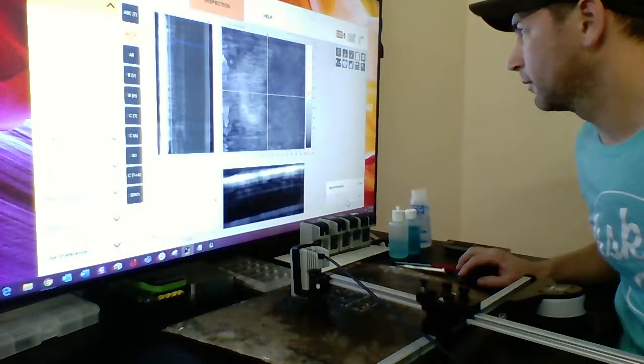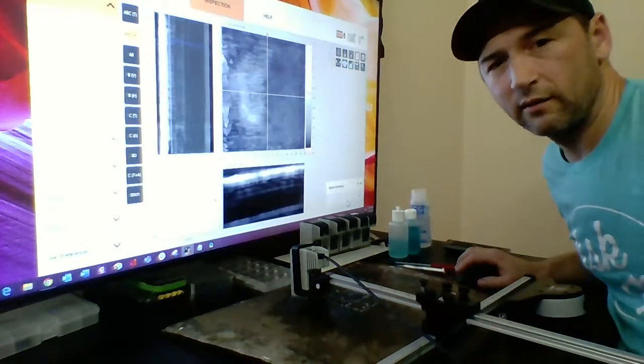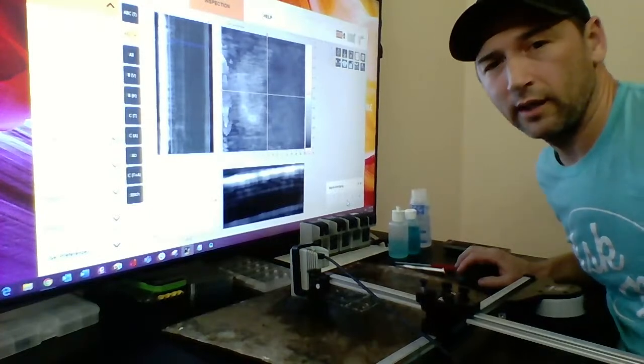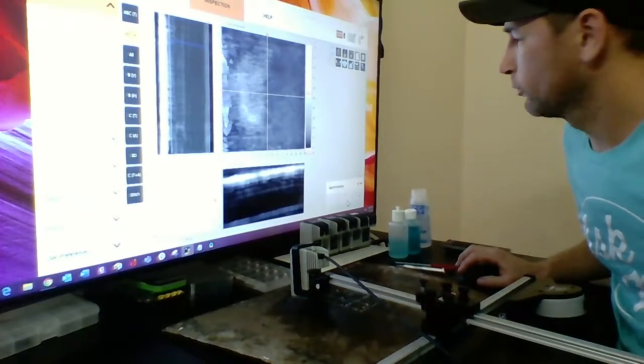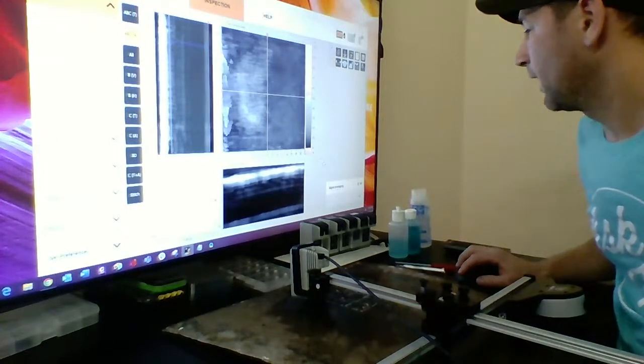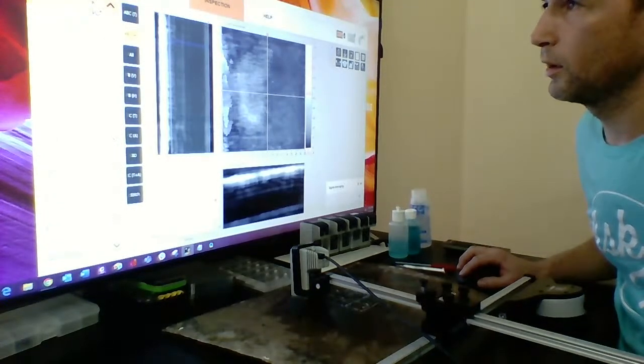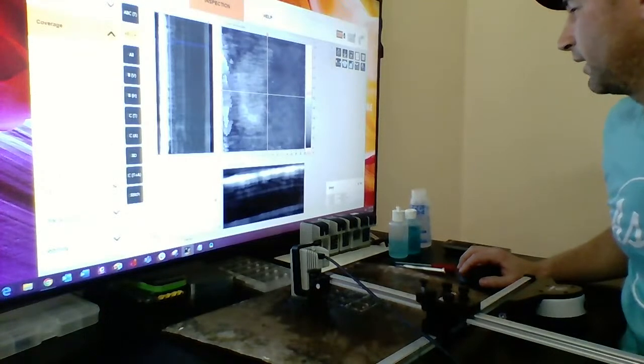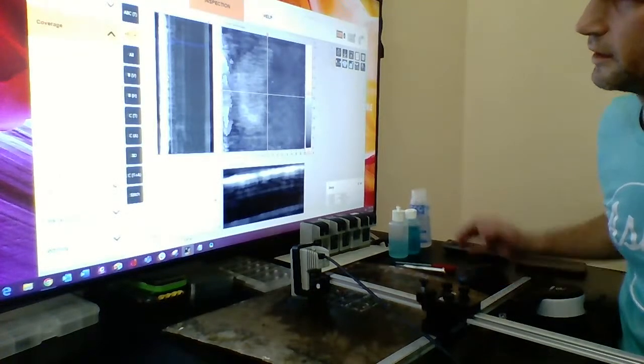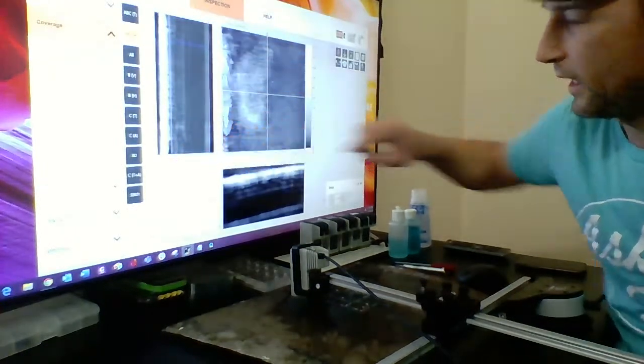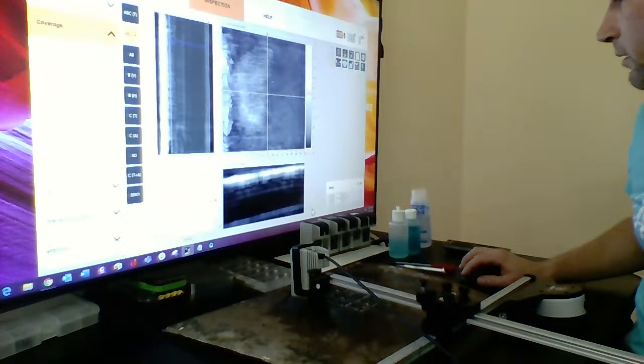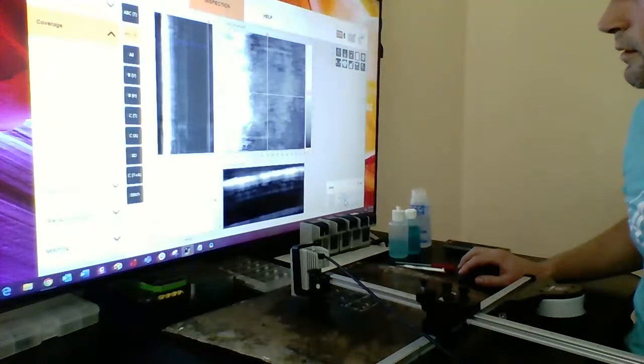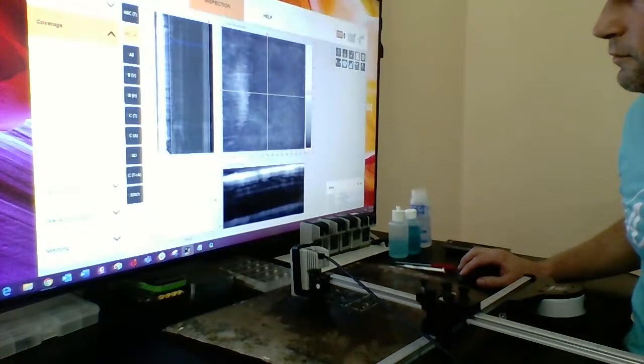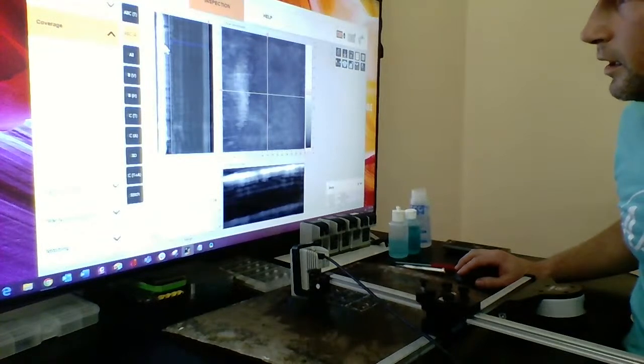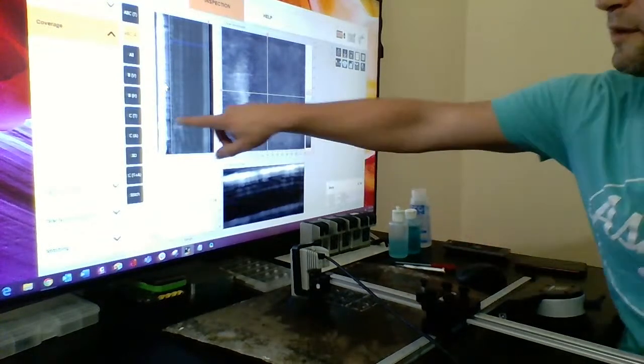We increase our scan speed when you decrease your sample rate, so you can scan much faster. Then what we're going to do is go into our coverage and take a look at our delay. This is where the interface gate is, and we're going to adjust that because it's coming right at 0. So let's adjust it so 0 is right at the interface, where the sound starts attenuating from the reflection.